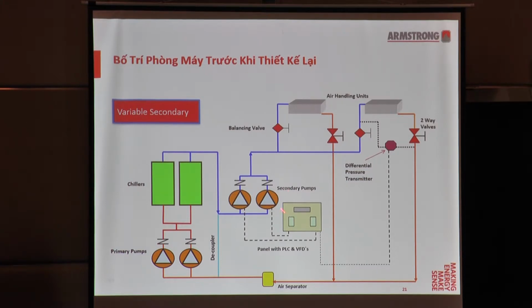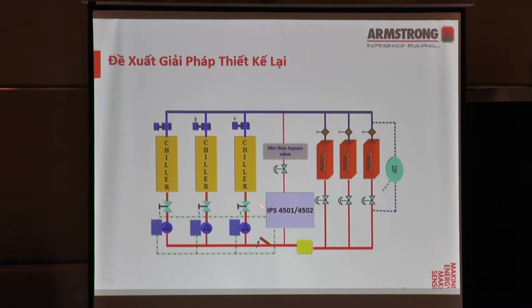you can see very well, right? You have a separate panel with PLCs and VFDs, and then the differential pressures and the valves, versus here, integrated, where you just have one attached DP sensor. So it actually helps you save overall, if you imagine this in the plant room, additional footprint savings as well.